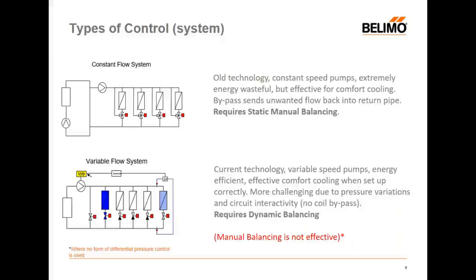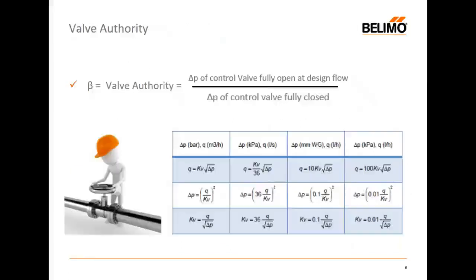So manual balancing valves are not really effective in this type of system where there is no other form of differential pressure control. If we're relying on a pressure dependent control valve and a manual balancing valve in a variable flow system, it's not ideal. It's old technology applied to new systems and it doesn't work very well. And we see that today in buildings where it's installed. We see a prevalence of low delta T, high energy bills, and inability to meet the comfort cooling requirements of the building.